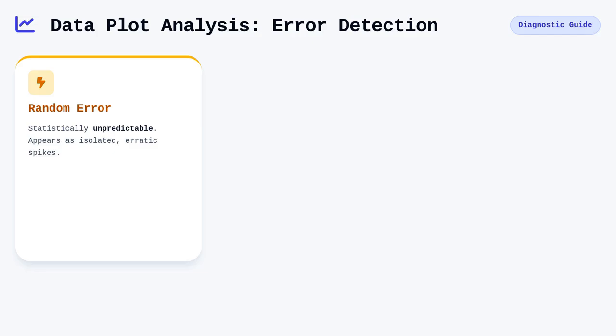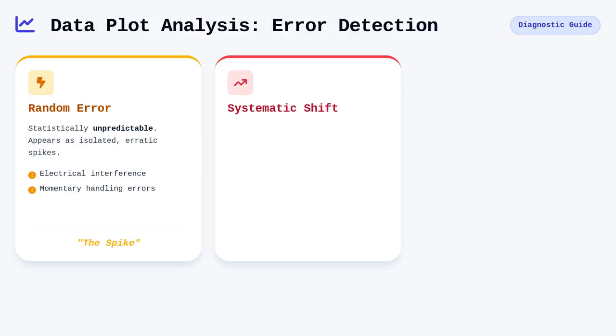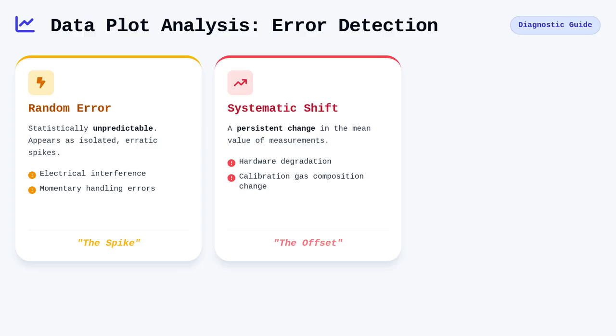When analyzing these plots, you must distinguish between a random error and a systematic shift. A random error is statistically unpredictable and often appears as an isolated, erratic spike in your data, which might be caused by a temporary electrical interference or a momentary handling error. A systematic shift is far more insidious because it represents a persistent change in the mean value of your measurements, pointing toward a degradation in sensor hardware or a change in the composition of your calibration gases.